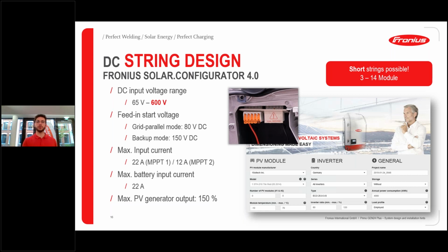So from 3 modules on, depending on the module you're using, you can do strings and connect it, and it is working. So a minimum of 3 modules per string is necessary, but that's really flexible when you think about a few roof systems where there is not enough space for a huge string. So then there you can also do a short string and connect it to the Primo without any issues.